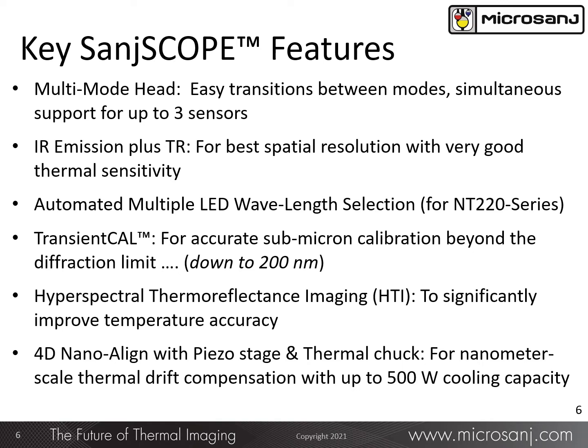Transient Cal enables thermal calibration for feature sizes below the diffraction limit. Auto positioning and autofocus is supported to compensate for sample movement during temperature cycling. This is an essential capability when investigating devices with submicron features.